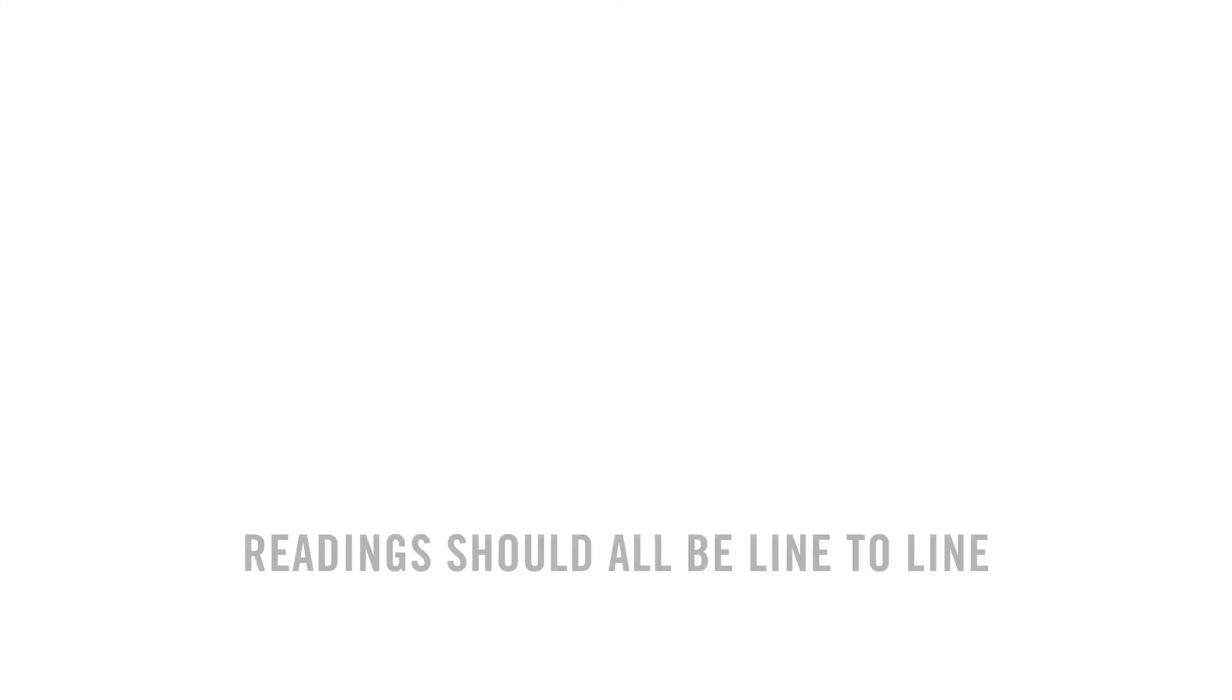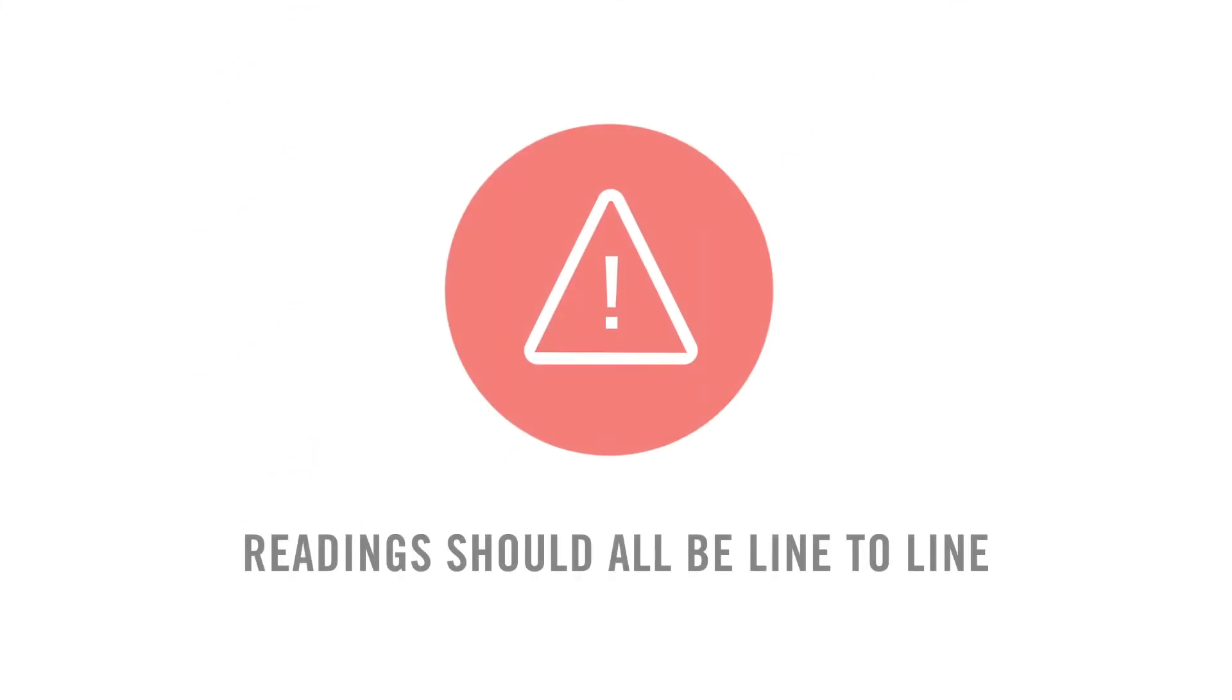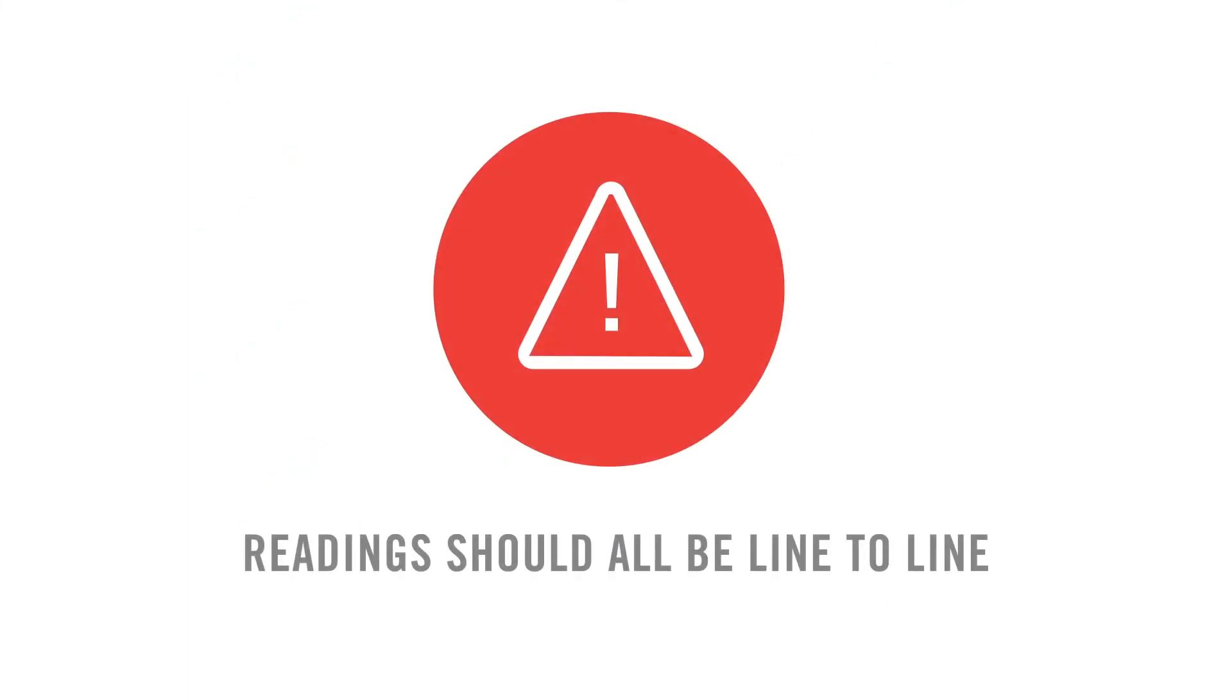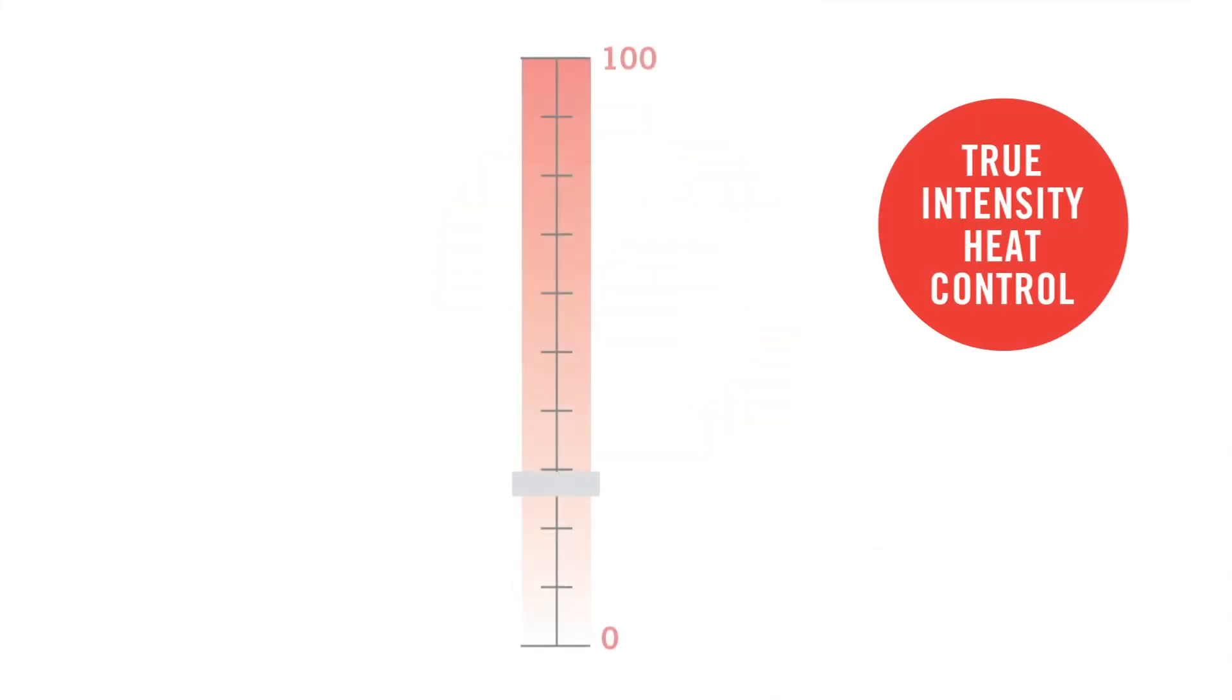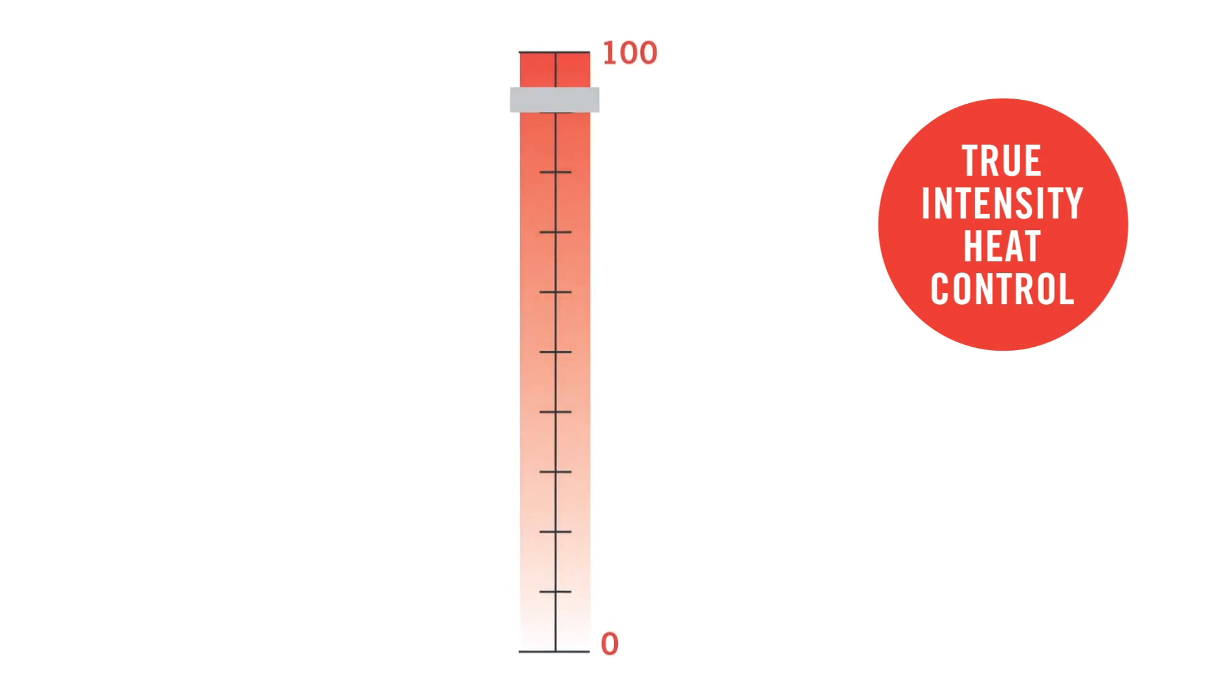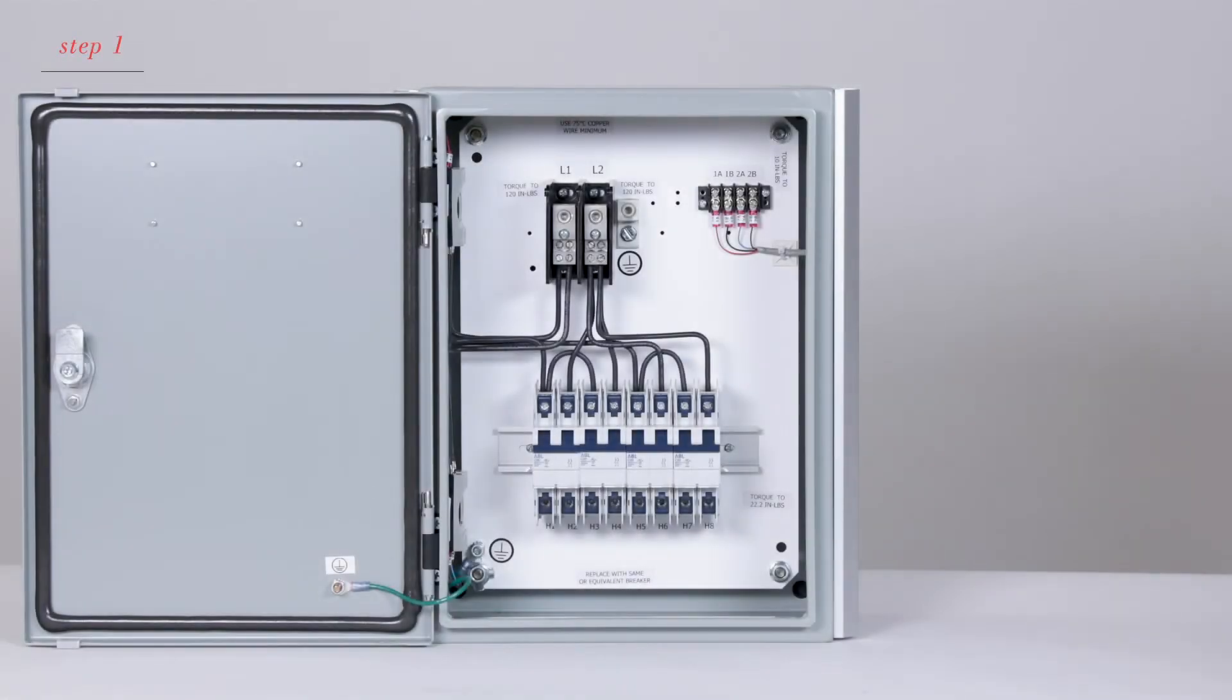Before you begin, please note, when you're taking readings, they should all be line to line, not line to ground. In addition, all readings should be taken with the heaters installed and a control signal of 100%. Let's begin.